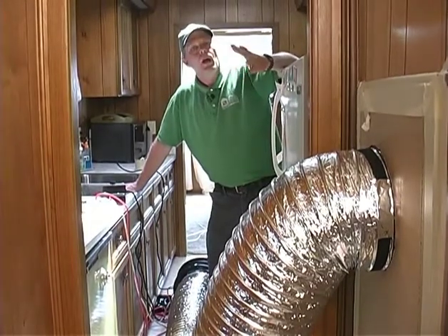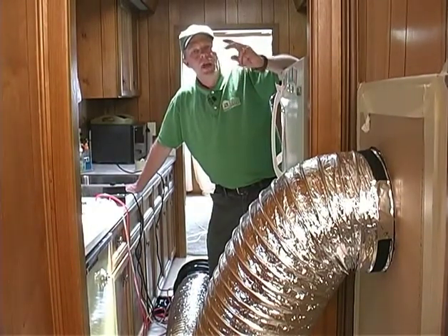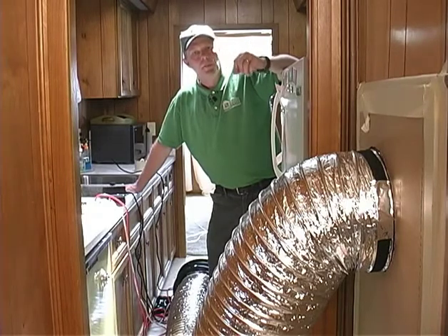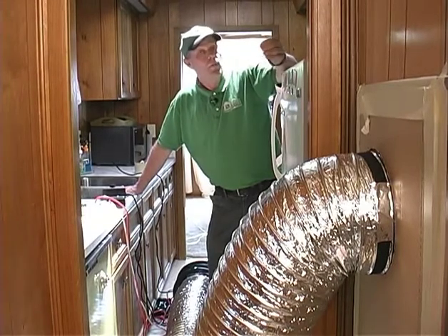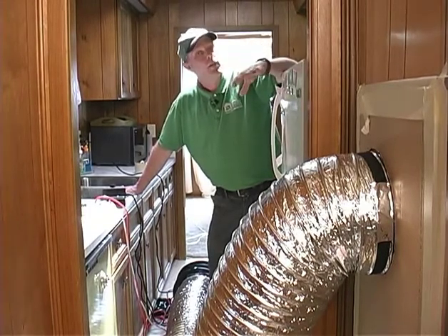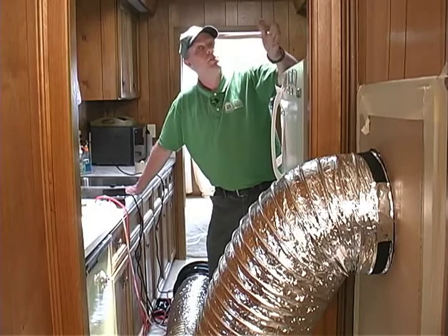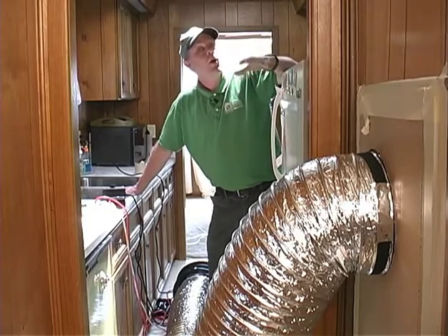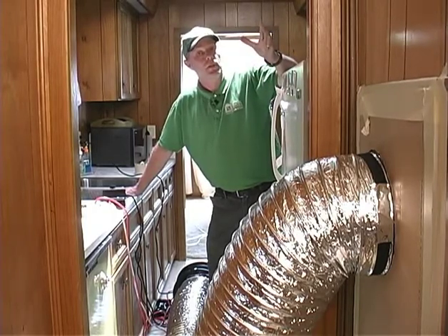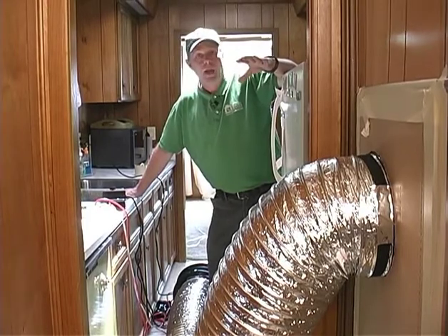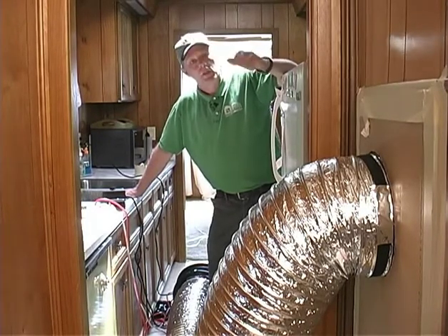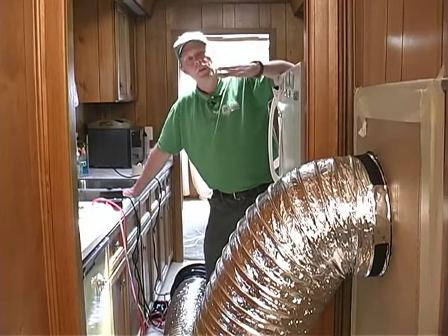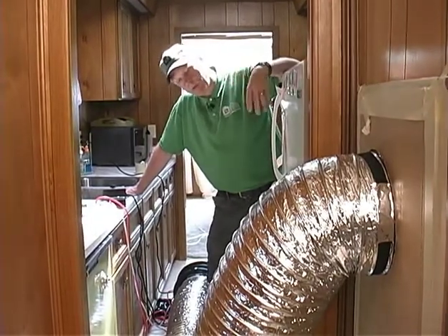and we are going to test the total duct leakage on this mobile home. There are two sides of a duct system: a supply side and a return side. Some mobile homes don't come with a return side. It's actually the front of the furnace that is the return duct. Some mobile homes do have a return system. This is not the case in this house. It's using the front of this furnace.